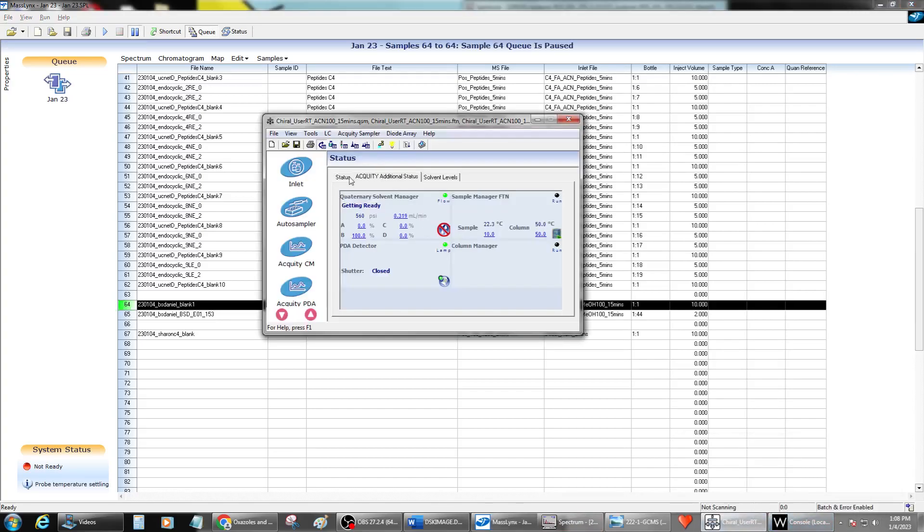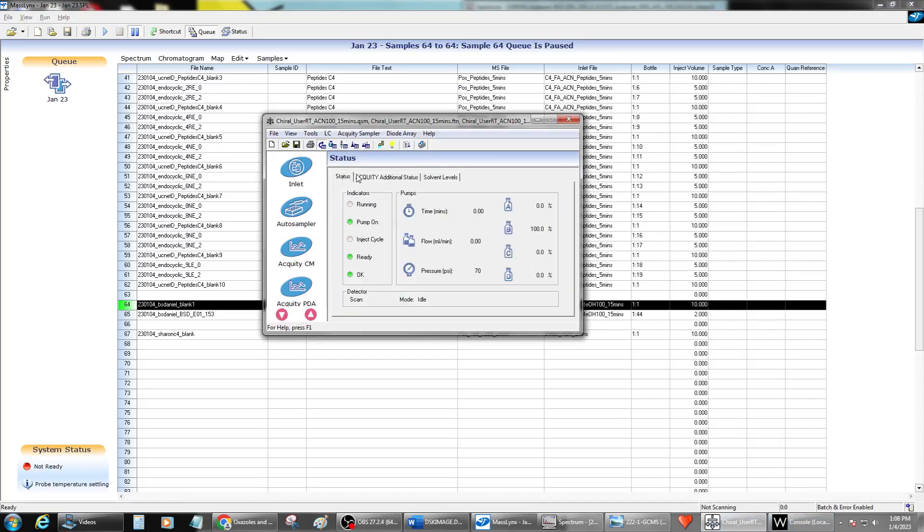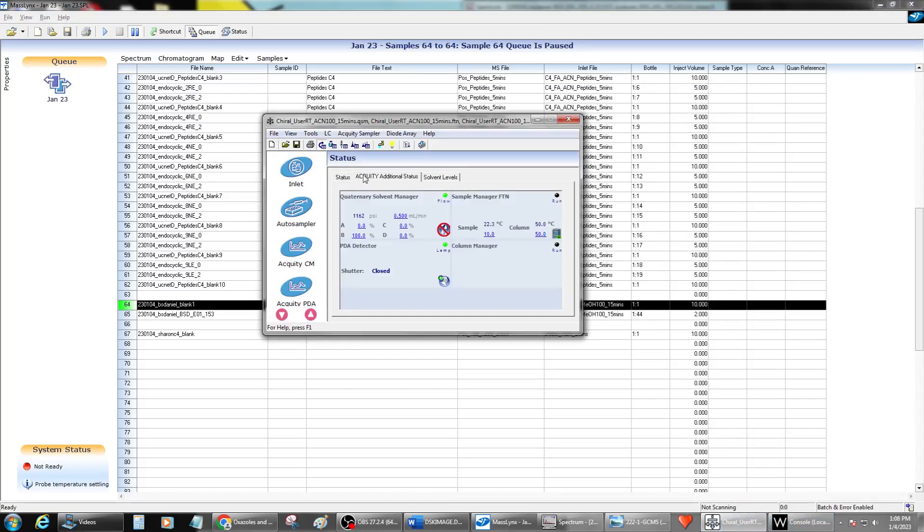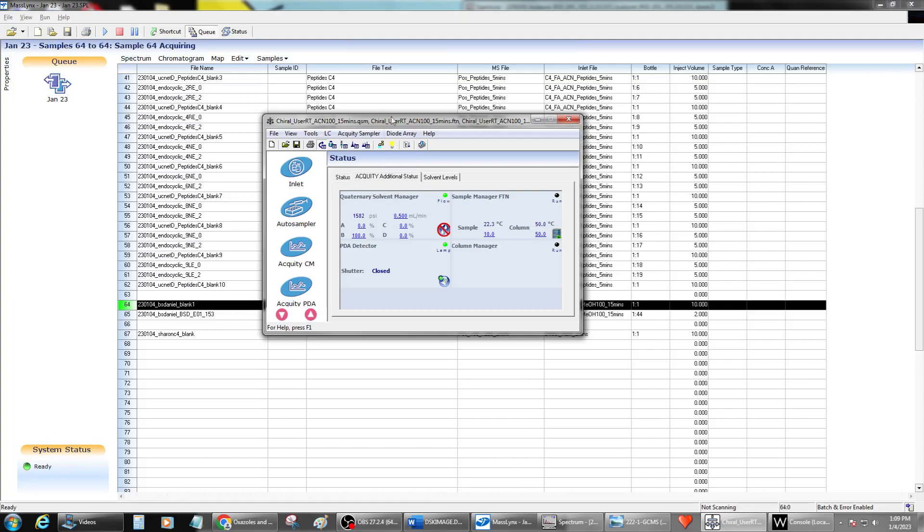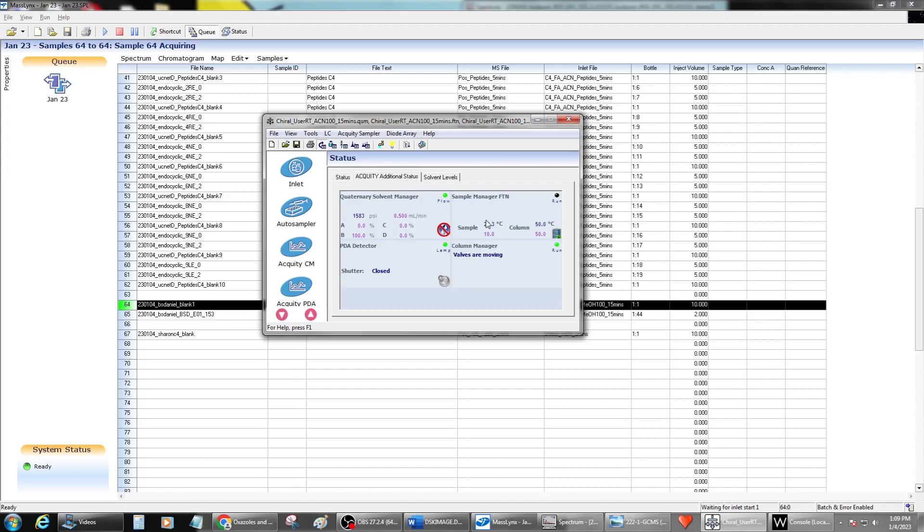And then I typically will wait around. Every now and again, this will not fix the missing, the error in the instrument. The sample manager actually won't start back up. And so I typically will look in the additional status signals in the ACQUITY tab in the inlet manager and make sure the sample manager starts working. So typically you'll see it start washing the needle and moving the needle. And once it says that, you know, you're pretty much good to go and go ahead and let it be.